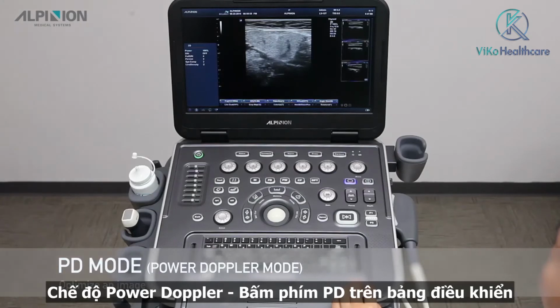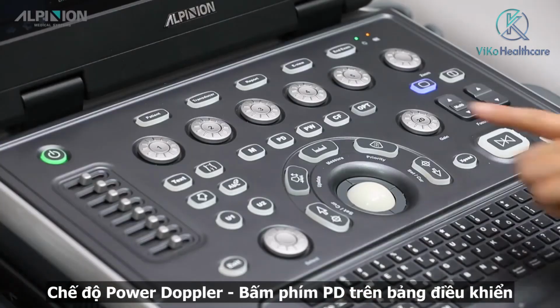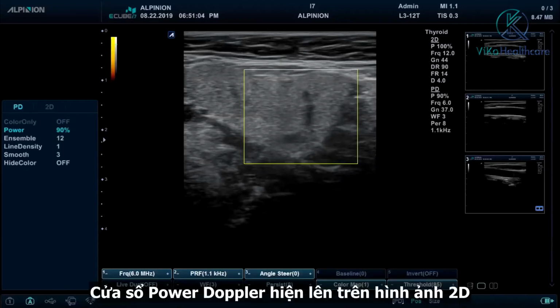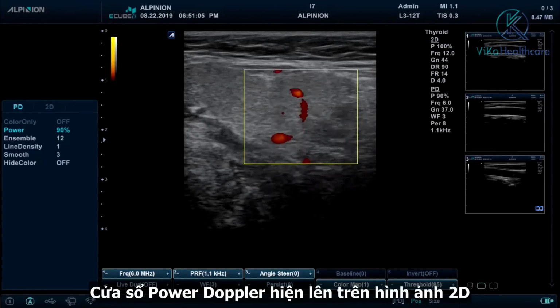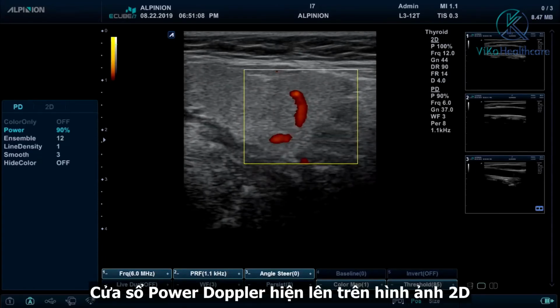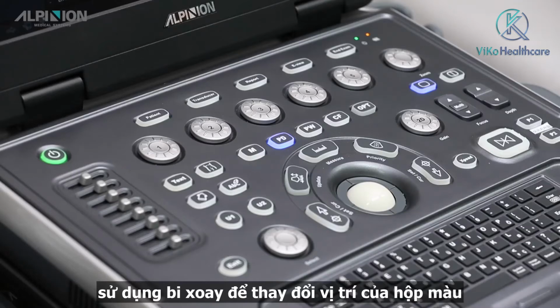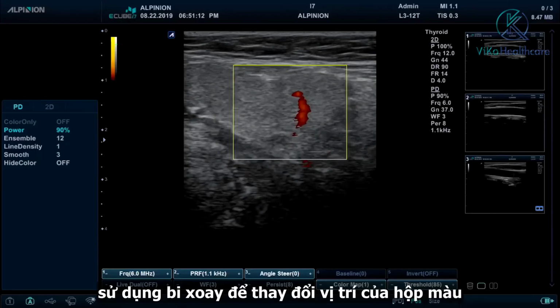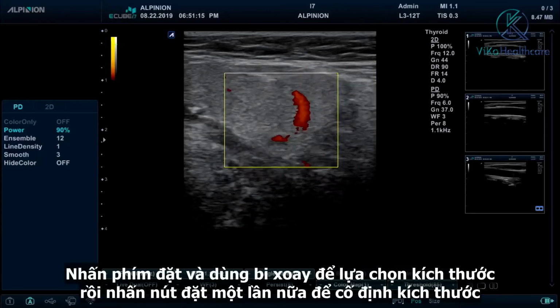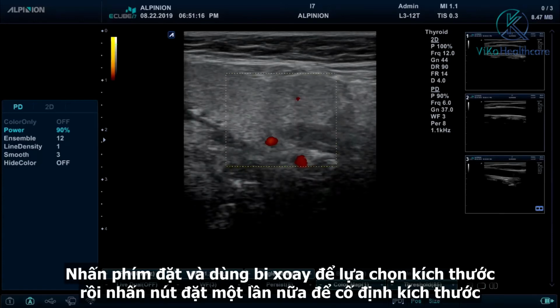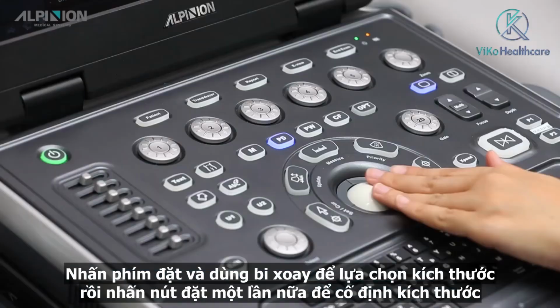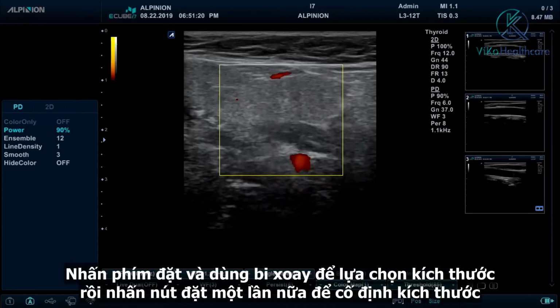Power Doppler mode. Press the PD key on the control panel. The Power Doppler window appears over the 2D mode image. Use the trackball to change the position of the color box. Press the Set key and use the trackball to change the size of the color box, and press the Set key again to fix the size.